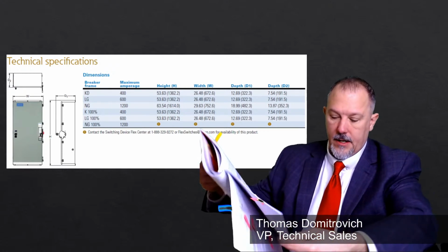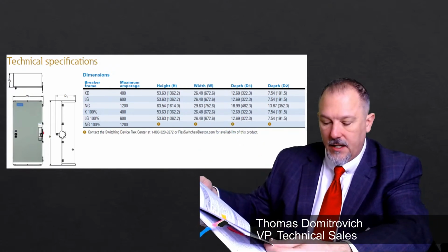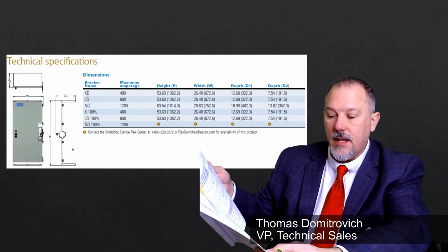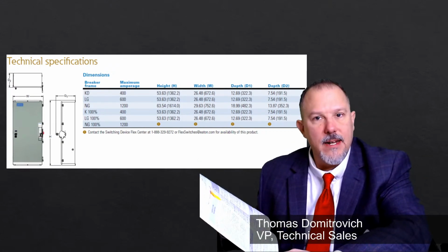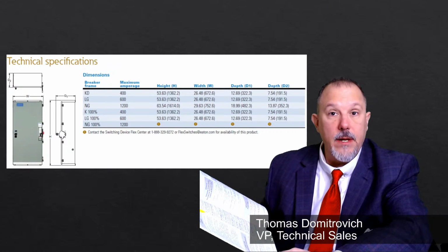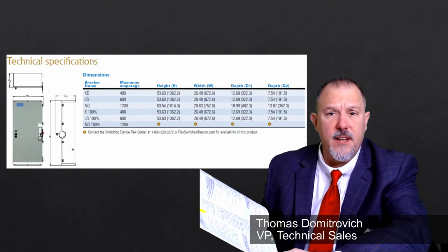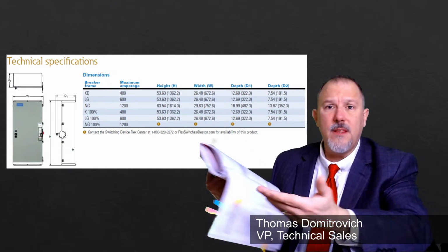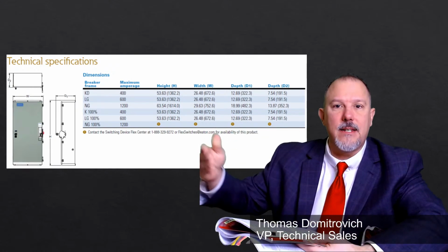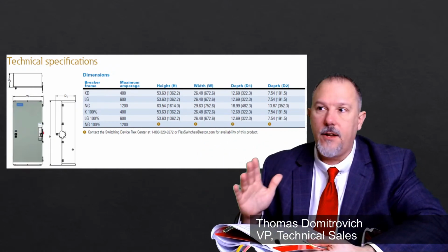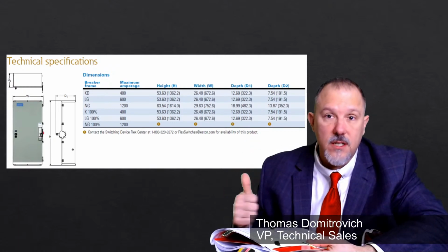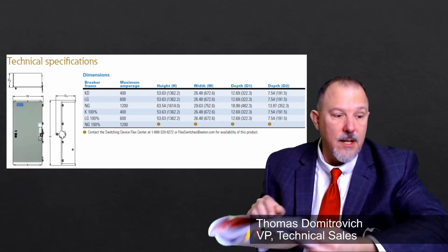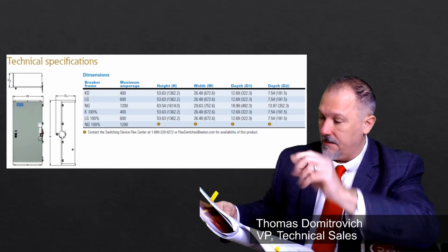Another area is 205, general maintenance requirements, and the single line diagram. Why do we need a single line diagram when doing maintenance? To figure out how to establish an electrically safe work condition. What better way than to put the only disconnect right next to the equipment? You don't need to go figure out where in the power distribution system your disconnect is. I've got 3 minutes.